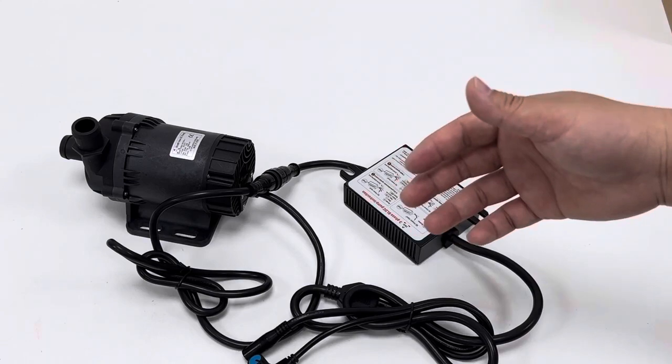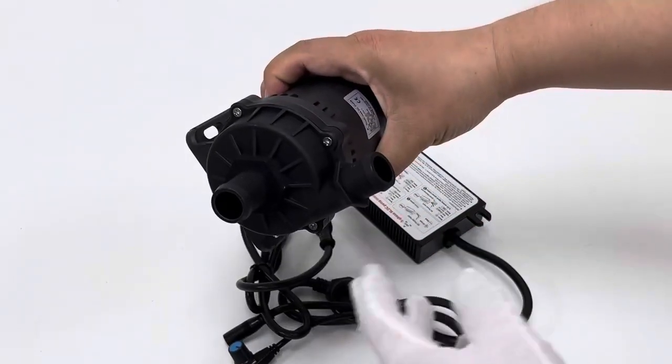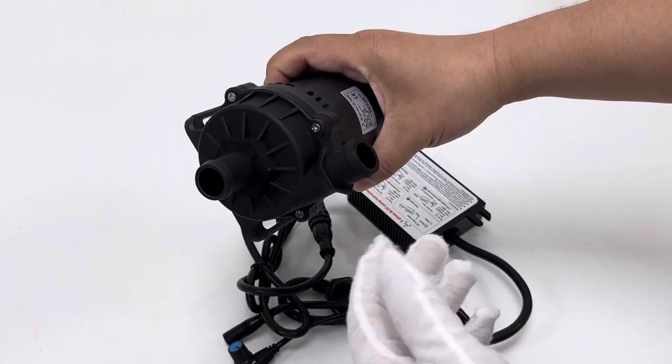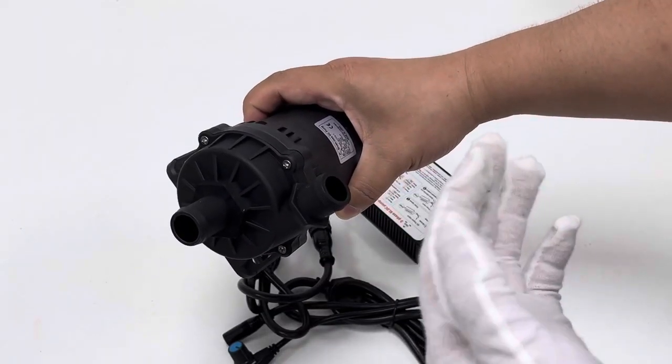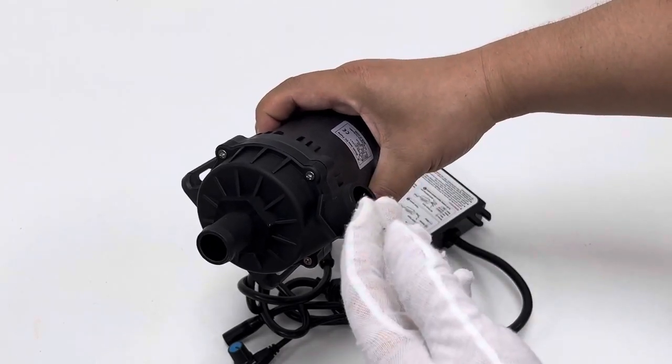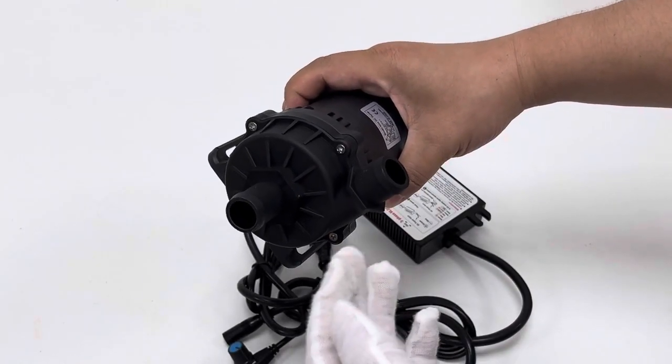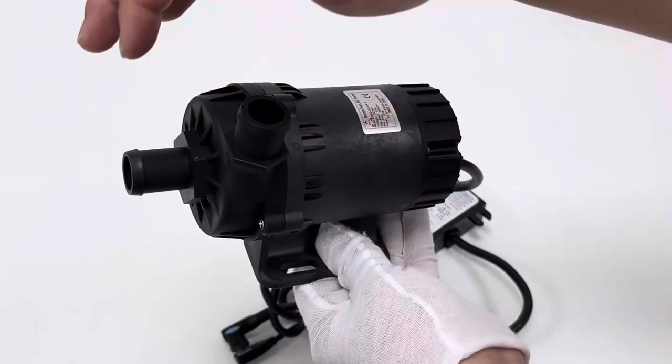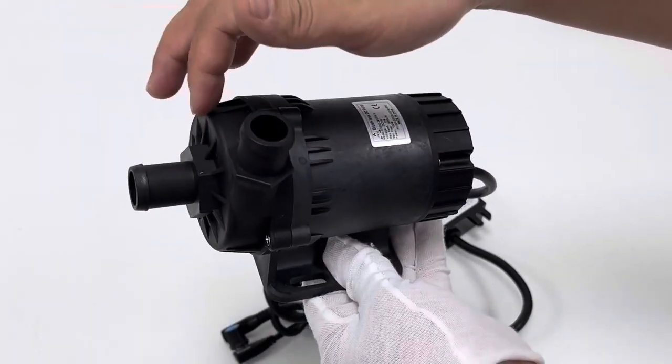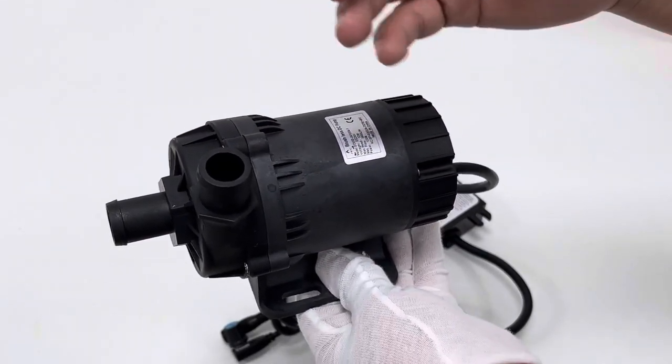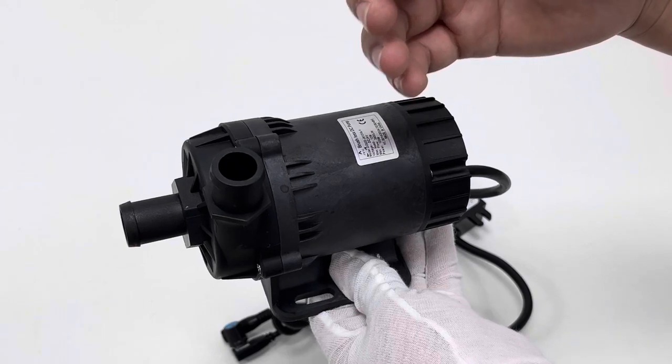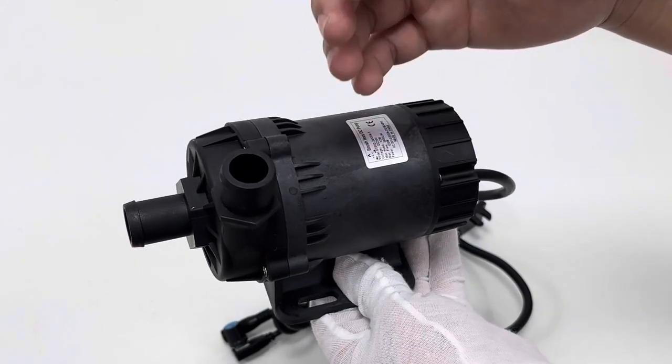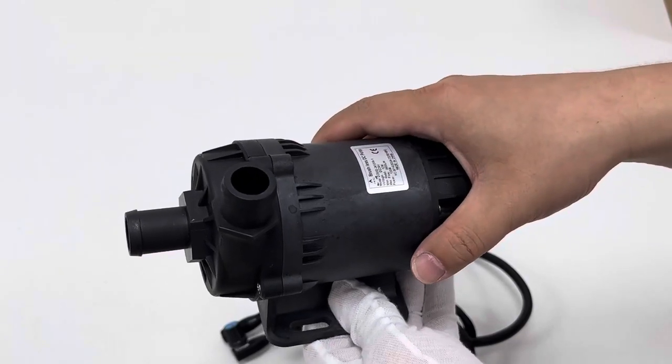One is dry-run protection mechanism. This pump works via the high-speed rotation of the pump. This pump is equipped with dry-run protection, which can help reduce the rotating speed of impeller when it is in the abnormal dry-run status, which can greatly reduce or alleviate the physical damage of heat generation in this abnormal scenario. A good feature.